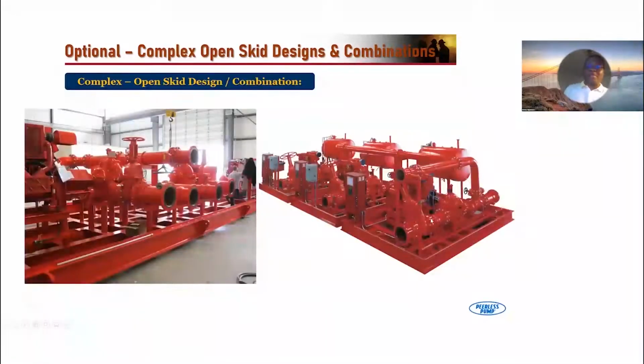We can even go one step further and make this a little more complicated, like a triplex situation where the customer needs 2 pumps as duty pumps and 1 as standby. Now we have 3 pumps on the same skid, all fully done with all the piping done. We break them down into single units, but we assemble them at the shop to make sure all 3 fit in with all the common header. You can see the common header right here, and then we break them up, and when you get to the job site, you can reinstall them.